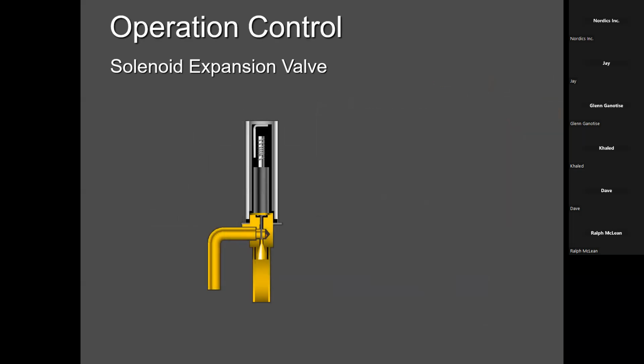So keep in mind, guys, this solenoid valve inside is all hard plastic. Nothing is metal there. A little bit of aluminum is available. But the biggest issue here is your plastic rotor. You have to be very careful when you're doing brazing. If at all you have to change this valve body for whatever reason down the road, please make sure you have your cold, damp cloth or a towel or something like that to keep it cool, so that the plastic does not melt. And then try your best to use oxyacetylene versus a propane tank. Oxyacetylene is much more precise, and it's basically brazing where you need, and nothing outside of that area. As you know, if you're using a B tank, the flame is kind of all over the place. So I would suggest you use an oxyacetylene tank when you're brazing on these tight spots.